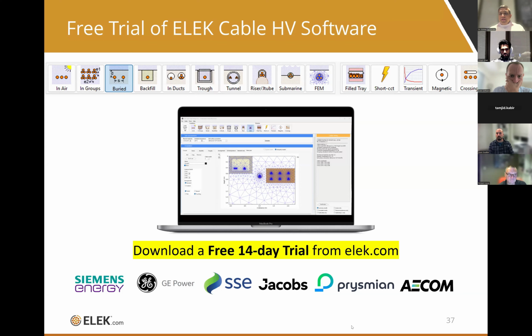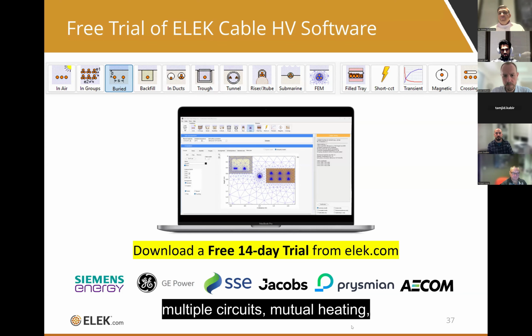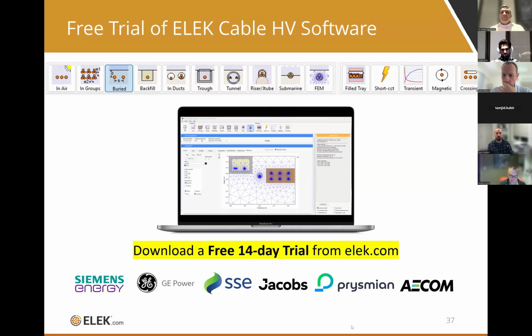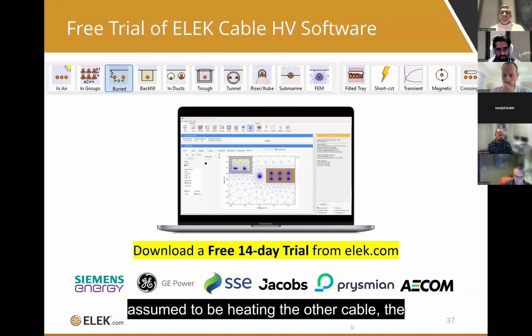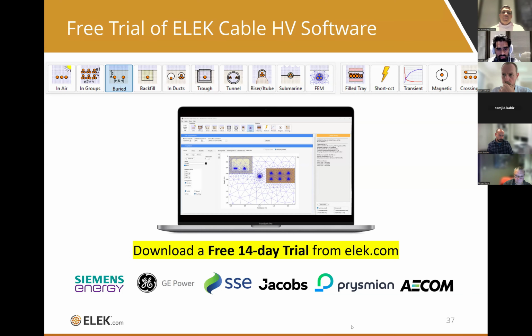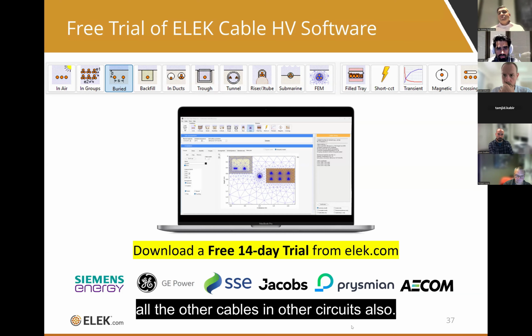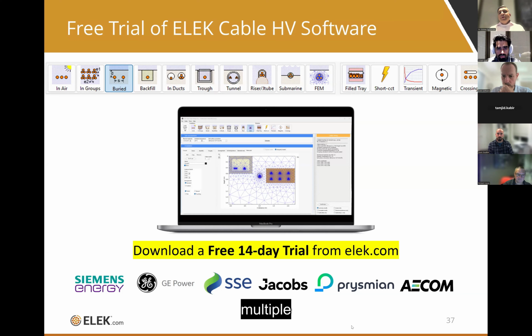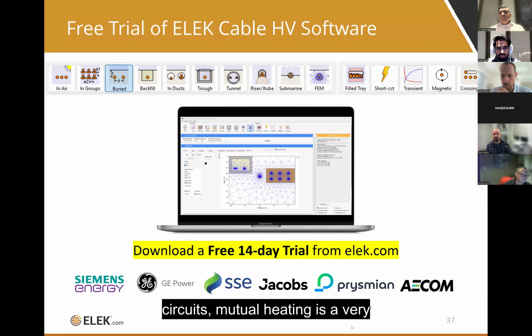Now, multiple circuits, mutual heating, how are they accounted for? Each cable in a circuit is assumed to be heating the other cables in the same circuit, as well as the cables in other circuits. So mutual heating between multiple circuits is a very important factor that has to be considered.